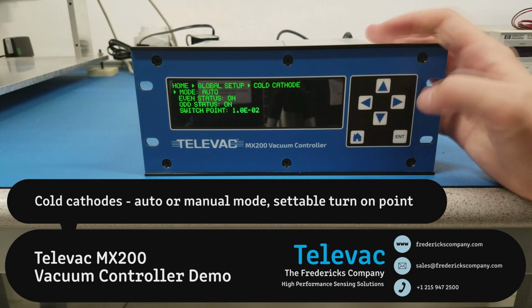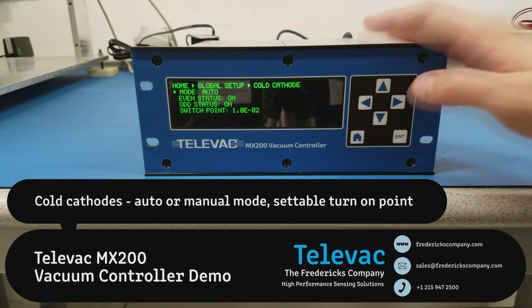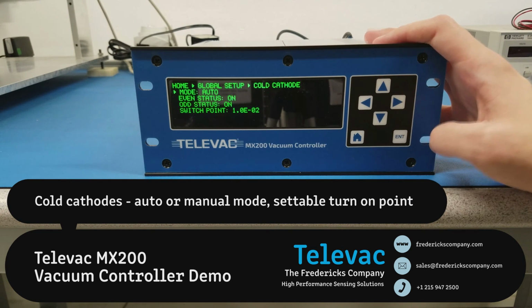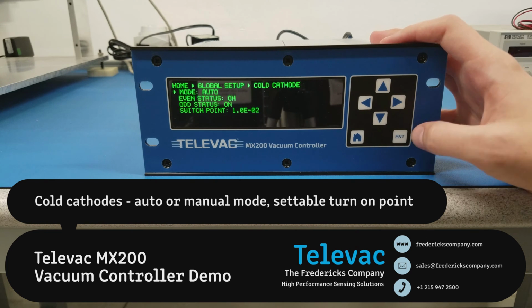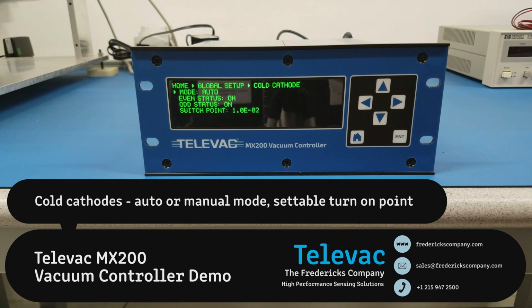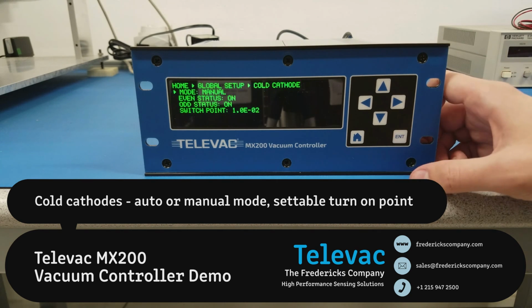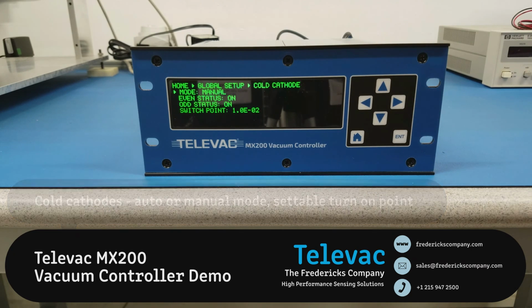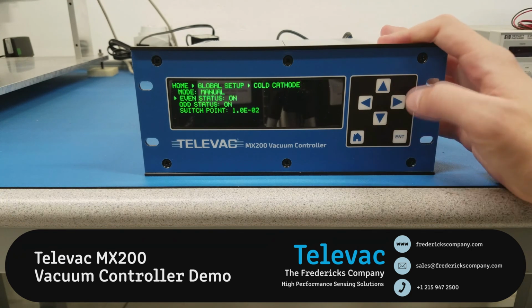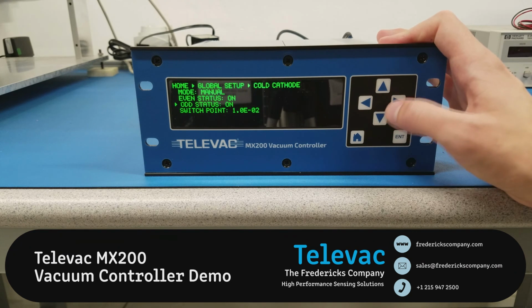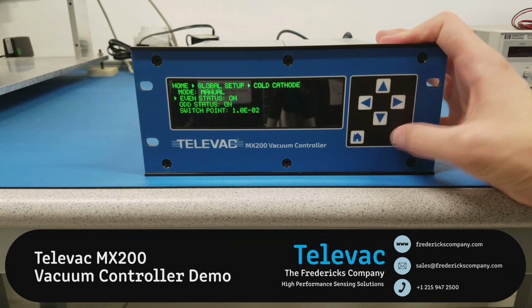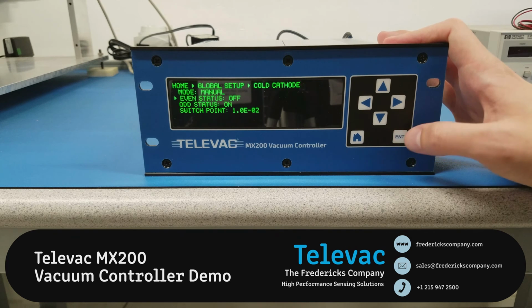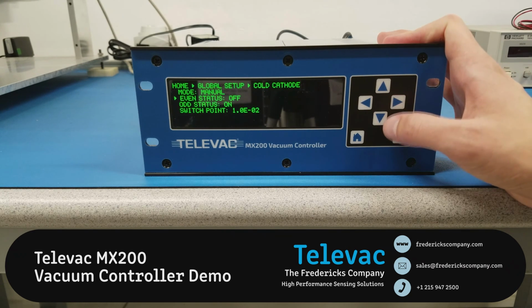Lastly, let's go to the cold cathode. So there are 2 modes for the cold cathode. It's either auto or manual. So auto is going to use the rough vacuum sensor, a 2A or 4A most likely, to turn on or off the cold cathode. And then you can hit enter on this, switch it to manual. So when it's in manual, you have to manually go into either the even stations or the odd stations and turn them on or off. And this is done again by pressing the enter key to toggle them on and off.